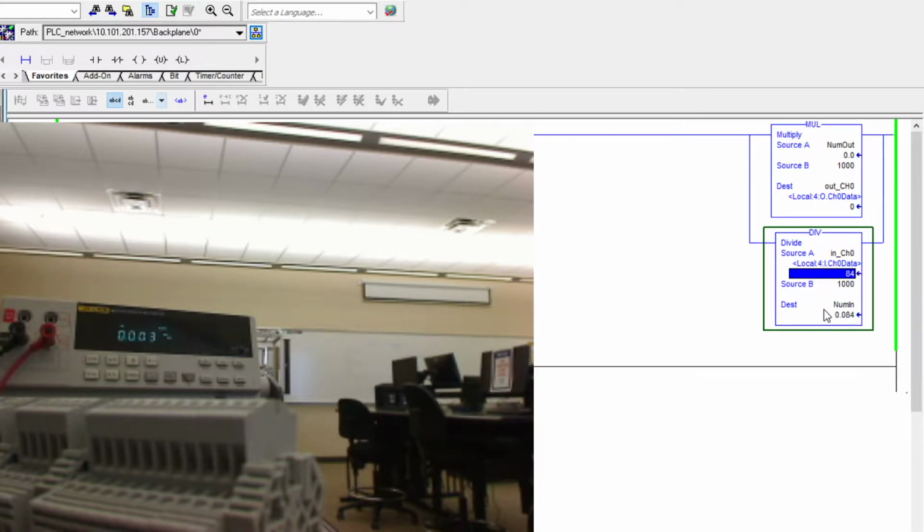But when we divide that by 1,000, we can see that that's way less than 1%. So it's bouncing around. Again, that's just noise in the system. This is a fast analog card, so it responds really fast. So any kind of noise, you see it pop up in there right away on this fast card. And so we're looking at 80 microamps of noise in the system.